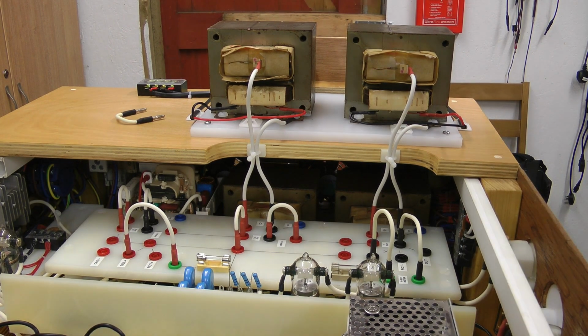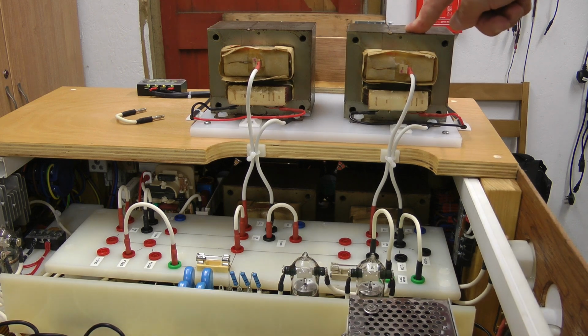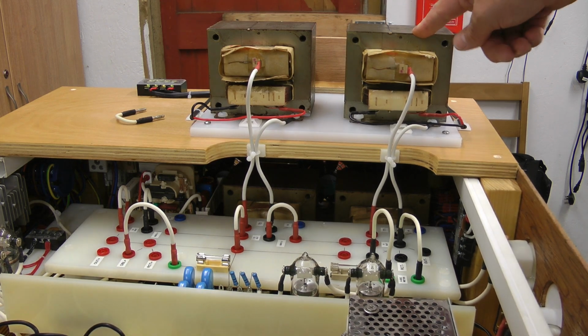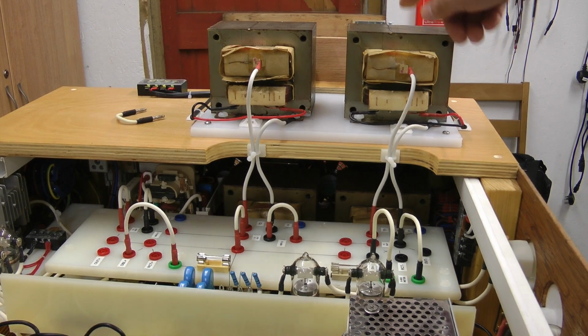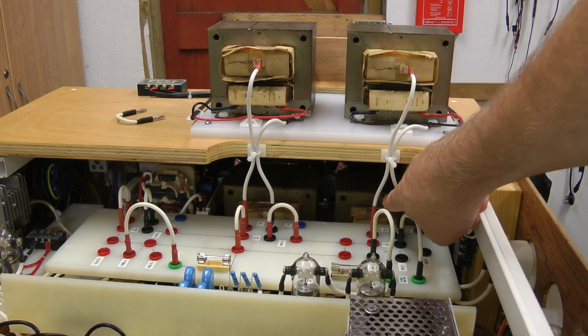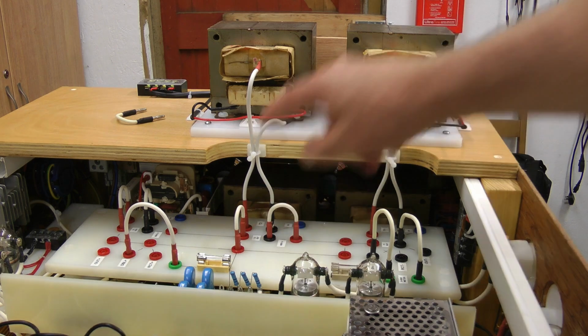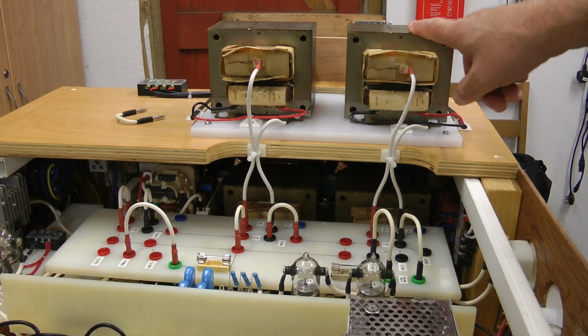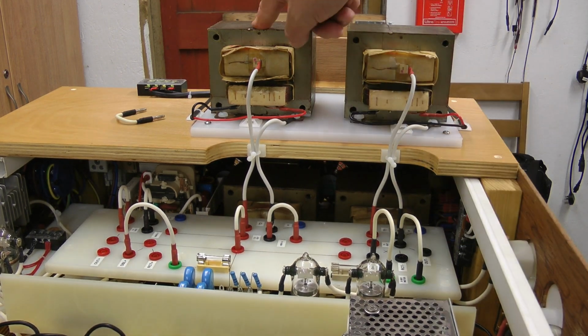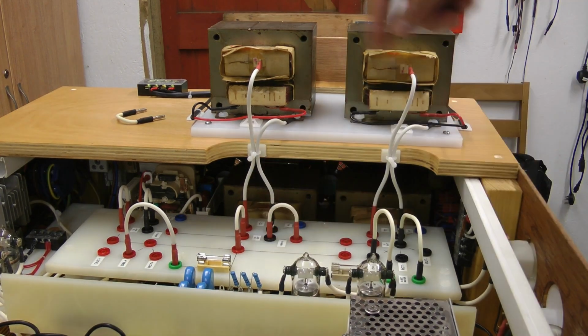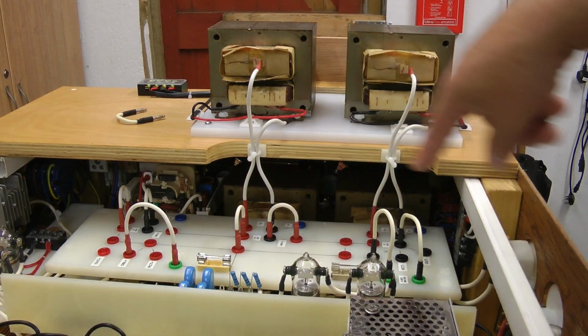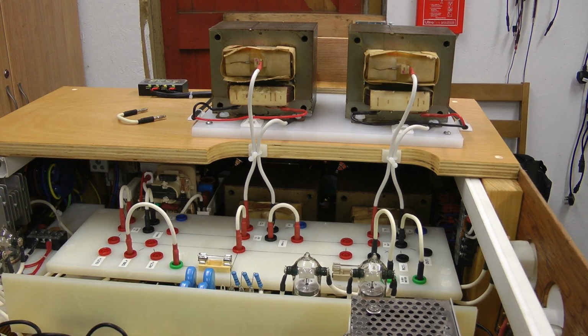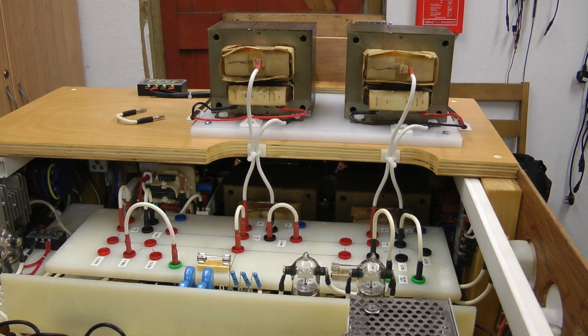So these 2 transformers are connected effectively parallel with each of their reciprocal transformers. So we've got transformer T1 is here, transformer T2 is here. Transformer T3 is in parallel with T1 and T4 is in parallel with T2, and these are connected in series via this patch board. So essentially we have 2 in series, 2 in parallel to make 4 1.8 kVA transformers. That's nominally 7 kVA worth of transformers.